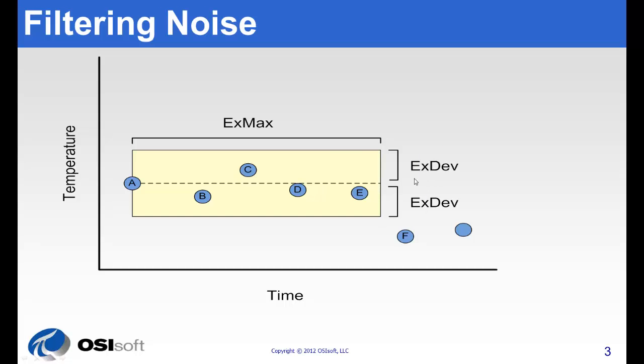We do that with two settings: with exception deviation, which defines the width of this dead band, and with exception maximum, which defines the maximum length of time to go before reporting a new value.